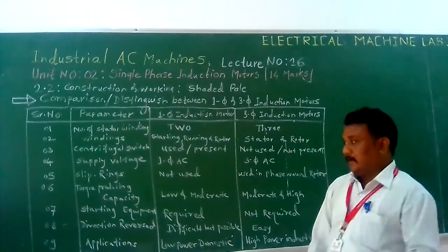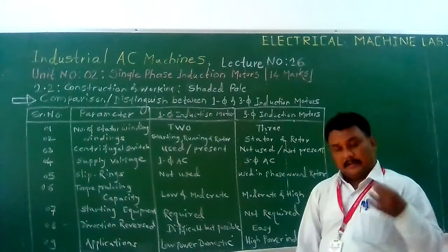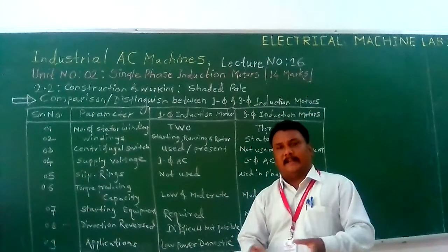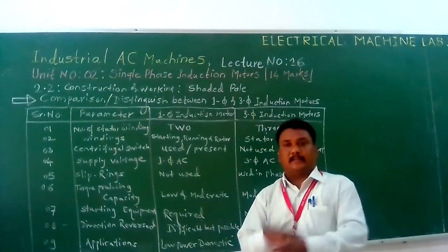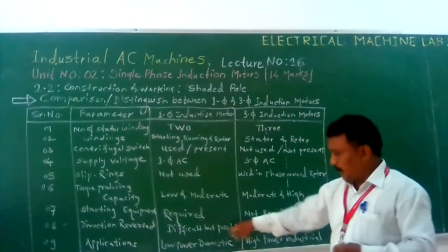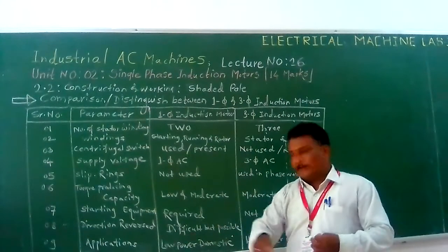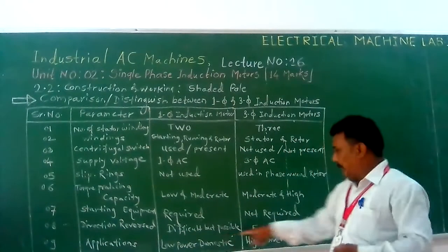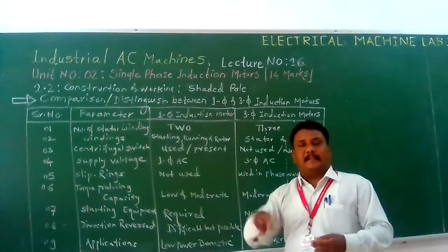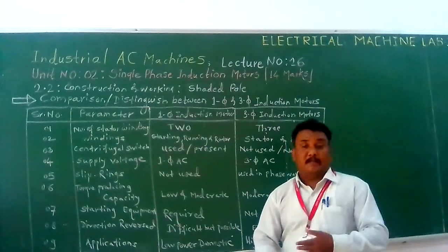Then the eighth parameter is direction reversal. In a single phase motor, with the starting winding and running winding, there are complications, so it is possible to reverse the direction but it is difficult. In a three phase induction motor it is easy. We know that if we change any two phases of the stator supply, the direction is automatically reversed.